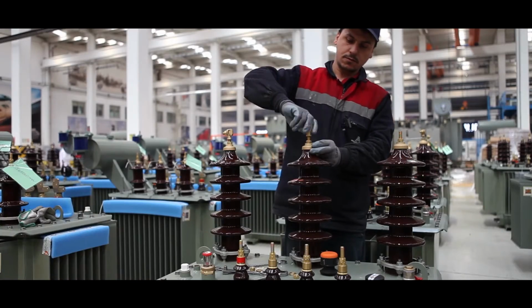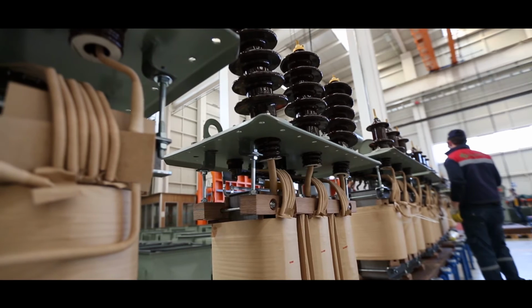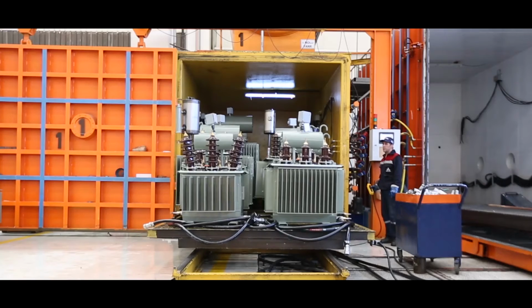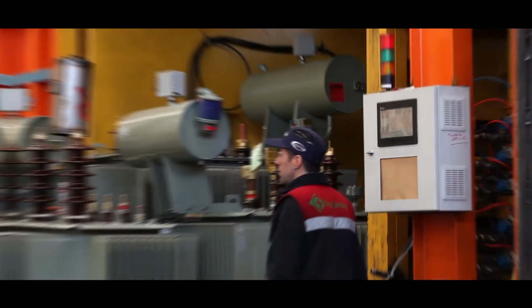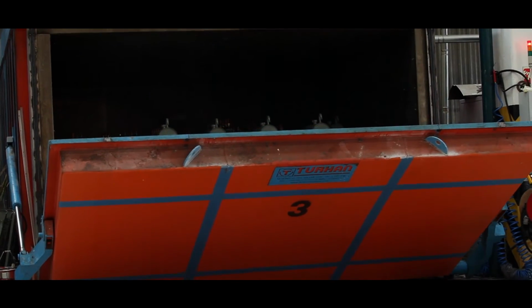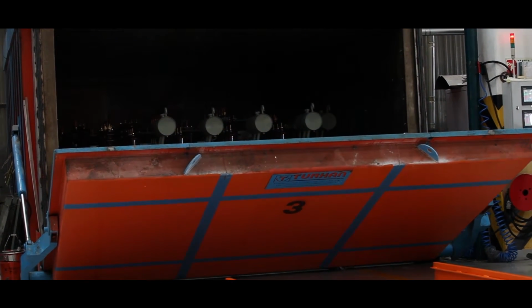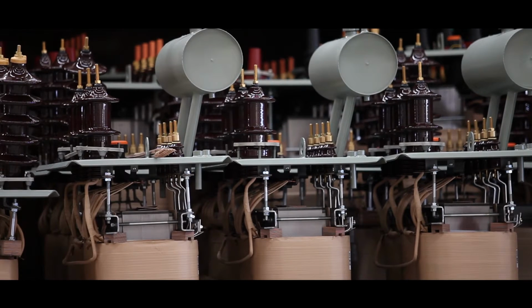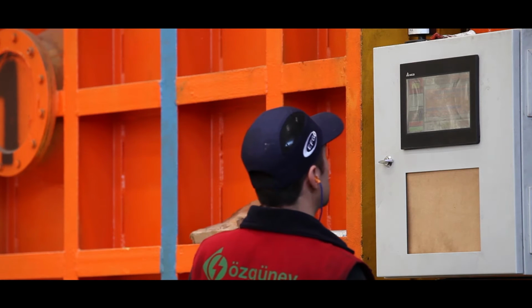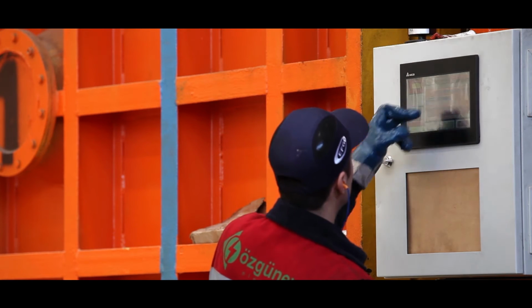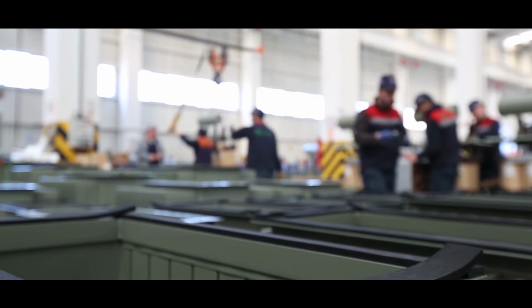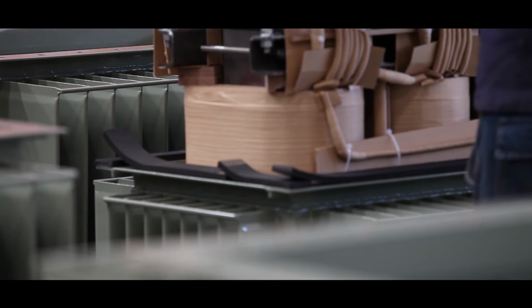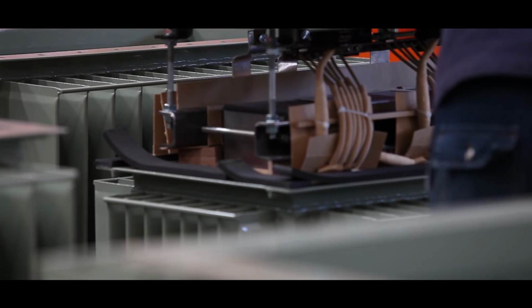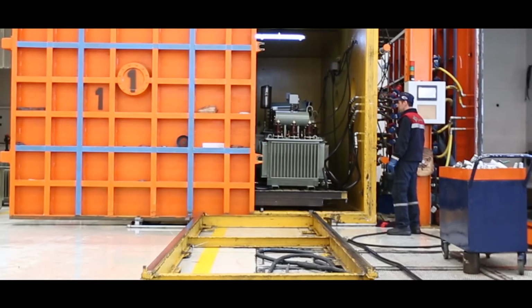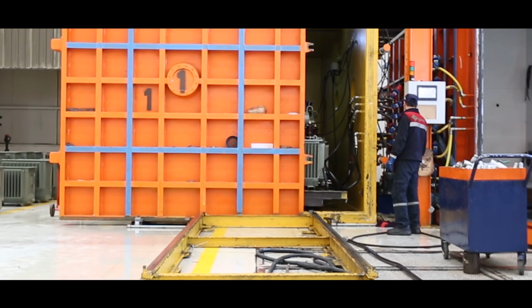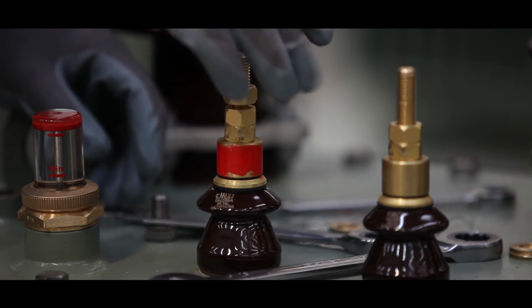Heating and suction is applied with our drying ovens at the determined temperature in order to dehumidify the solid insulating materials of the mobile part. Thus, the maximum drying process is performed. The humidity and temperature values in our ovens are constantly analyzed and evaluated via the charts on the digital screens. After removing the mobile part from our drying ovens, it is placed within the boiler at a temperature of 20 degrees Celsius within 15 minutes at utmost. Oil filling is performed in a suction environment at predetermined temperatures within the oil-filled suction ovens. Finally, the mounting process is completed by attaching accessories such as the indicator valve, throttle, thermometer, etc. on the oil-filled transformer and submitting to the testing division.